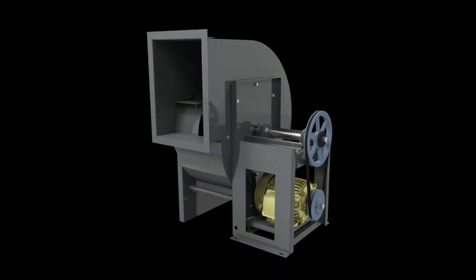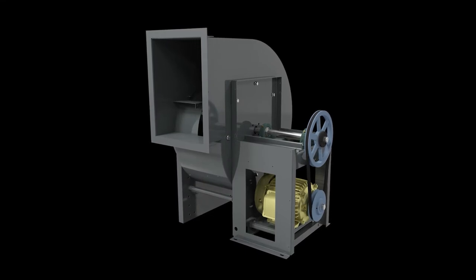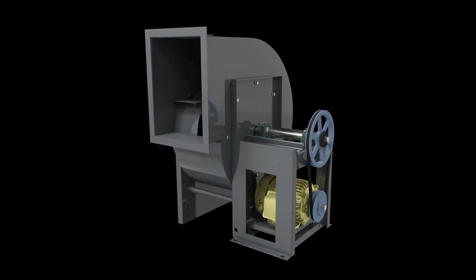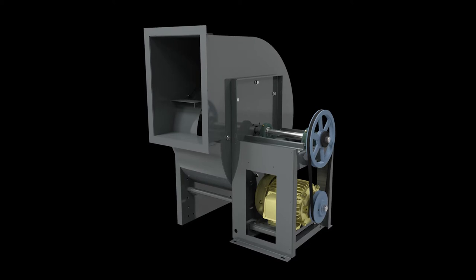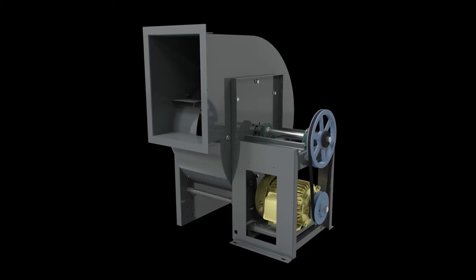To illustrate, we are utilizing a single wide, single inlet, light duty blower, often referred to as a utility set or vent set. The fan has a non-ducted inlet and a length of duct connected to the discharge, a common setup in fan testing. Our duct is the same size as the fan discharge and is 48 inches long. How important is the length of the discharge duct? Let's take a closer look.